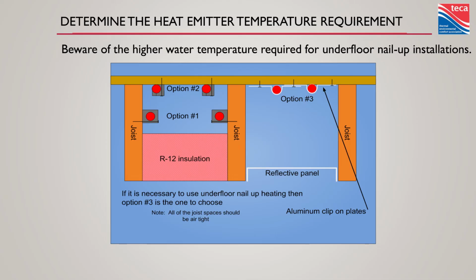If we pop over to the left here, this is just a couple of pipes nailed up with tube talons. So for those of you who are billiards folks, you probably know just how much contact a round surface has with a flat surface. There's very little conduction happening there. We're just hoping to heat up a pocket of air, and hopefully that's going to heat up the floor enough to hopefully heat the space. You're going to need higher water temperatures with a system like that, and ultimately that's going to affect your heat pump's performance.